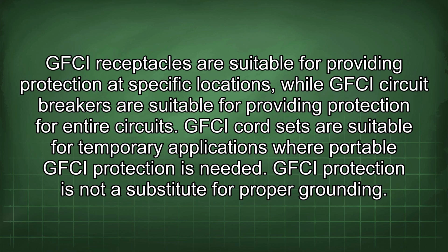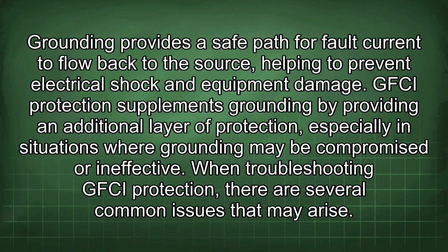GFCI protection is not a substitute for proper grounding. Grounding provides a safe path for fault current to flow back to the source, helping to prevent electrical shock and equipment damage. GFCI protection supplements grounding by providing an additional layer of protection, especially in situations where grounding may be compromised or ineffective. When troubleshooting GFCI protection, there are several common issues that may arise.